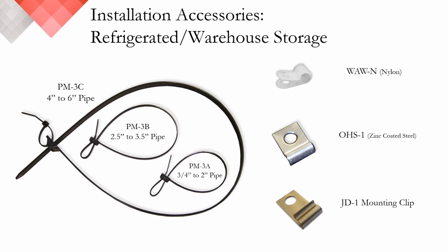Of course, this is specific to in-rack detection. At the ceiling level, the opportunity for damage is greatly reduced. In this area, it would be advisable to follow the sprinkler pipes and attach directly to it if at all possible and permitted, again, according to your jurisdiction and your AHJ. To do so, we recommend double-loop pipe straps. These provide your installers the ability to cinch the cable tie to the pipe securely without compromising the actual detector. The first loop serves as your primary anchor to the pipe, whereas the second loop provides taut but loose support to the detector to avoid damage.